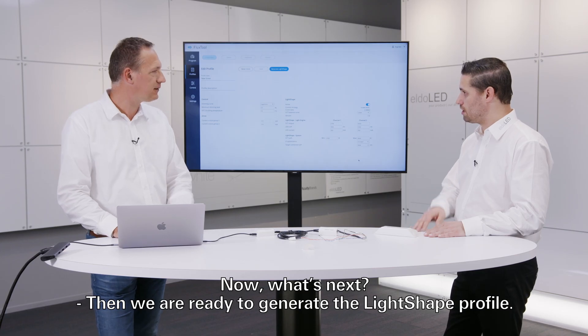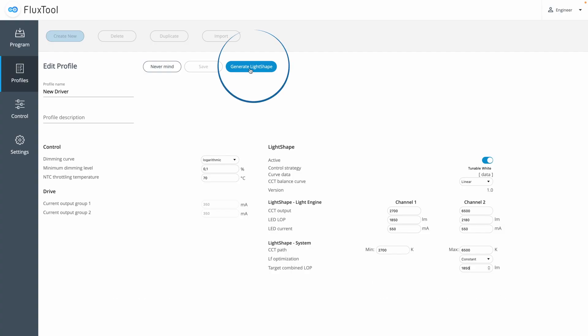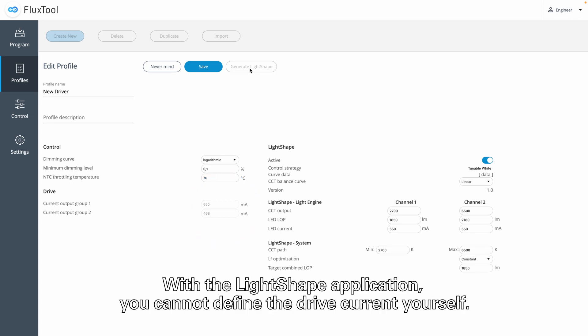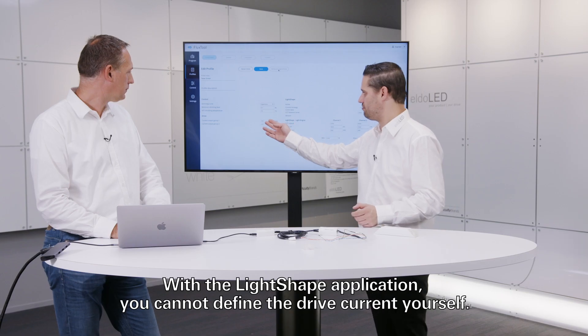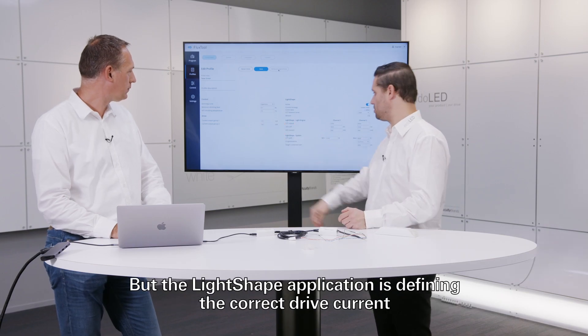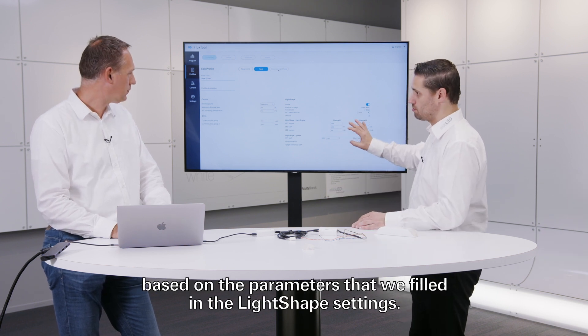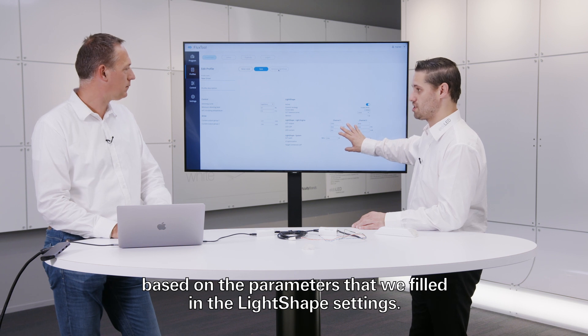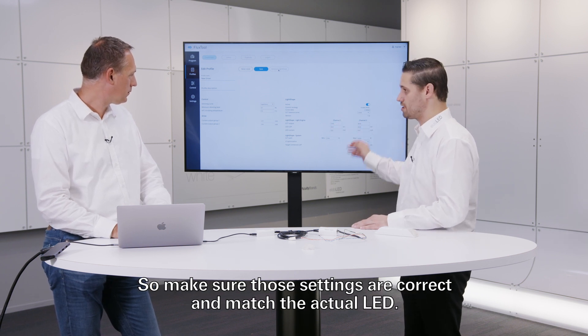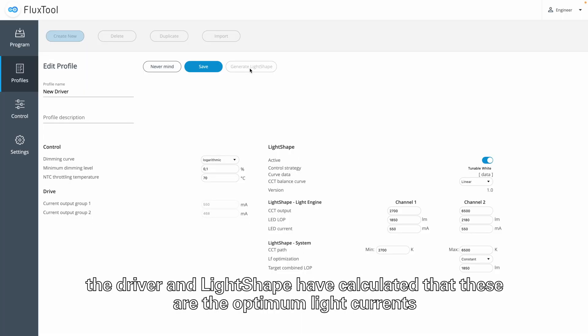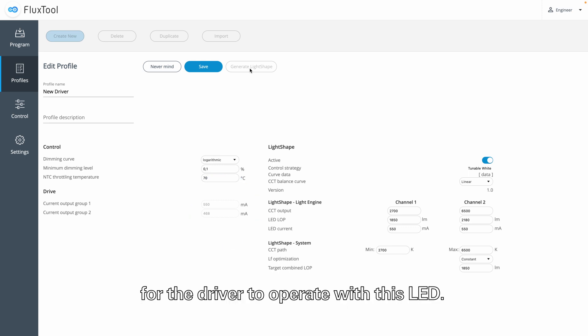Now we are ready to generate the light shape profile. You would see that the actual drive currents are changed. With a light shape application you cannot define the drive current yourself — the light shape application defines the correct drive current based on the parameters we filled in. So make sure those settings are correct and matching the actual LED. In this case we did. The driver and light shape has calculated the optimum drive currents for the driver to operate with this LED.